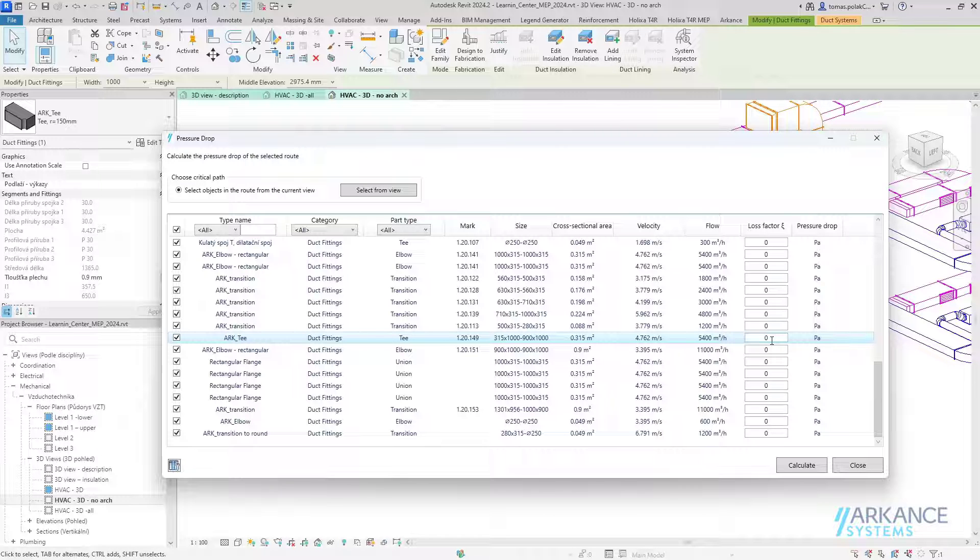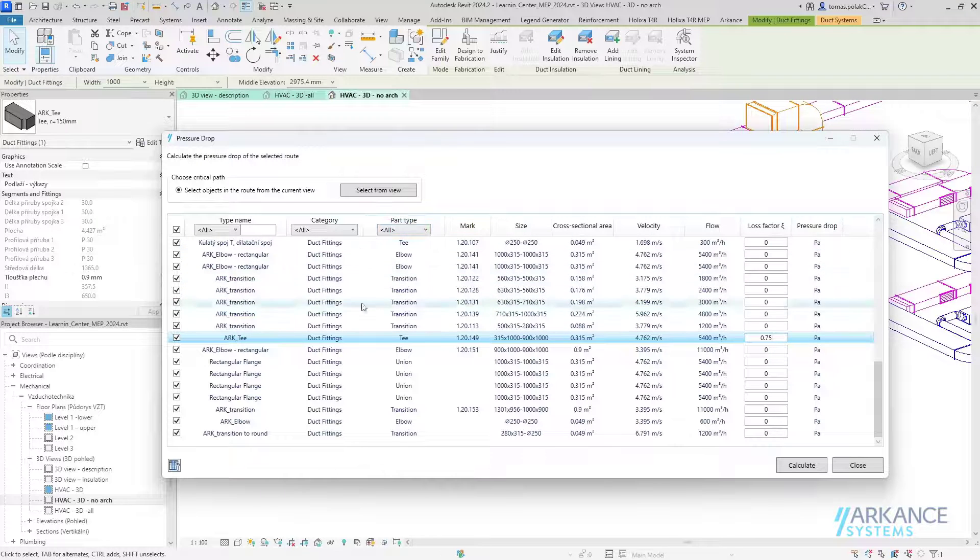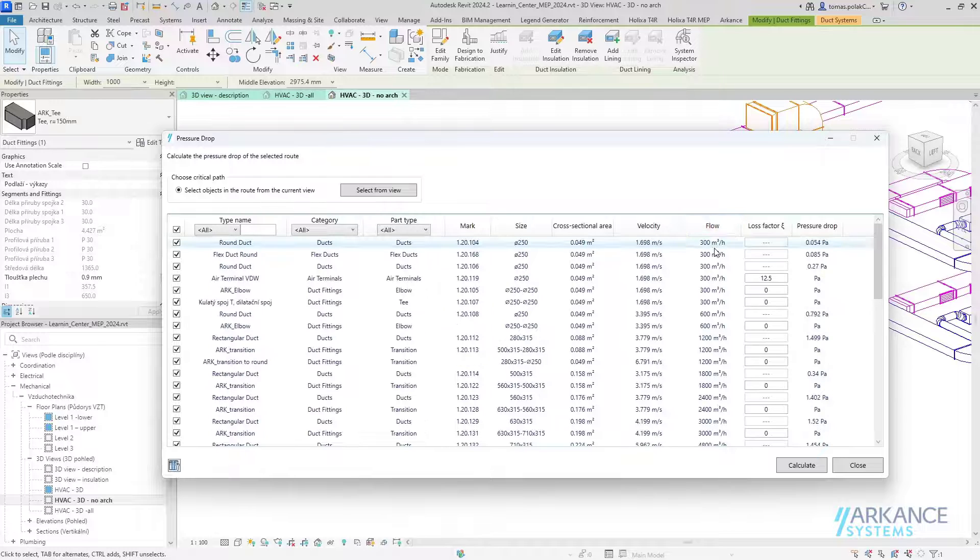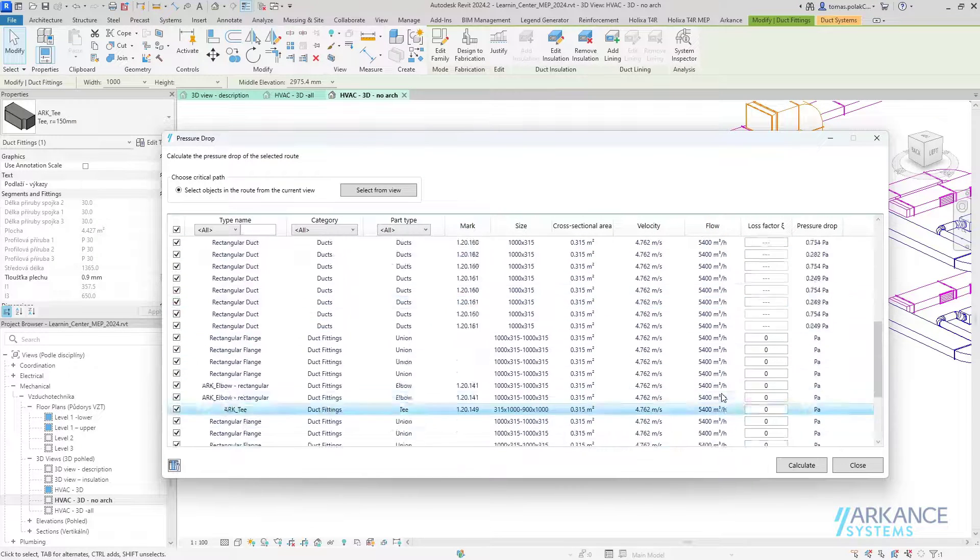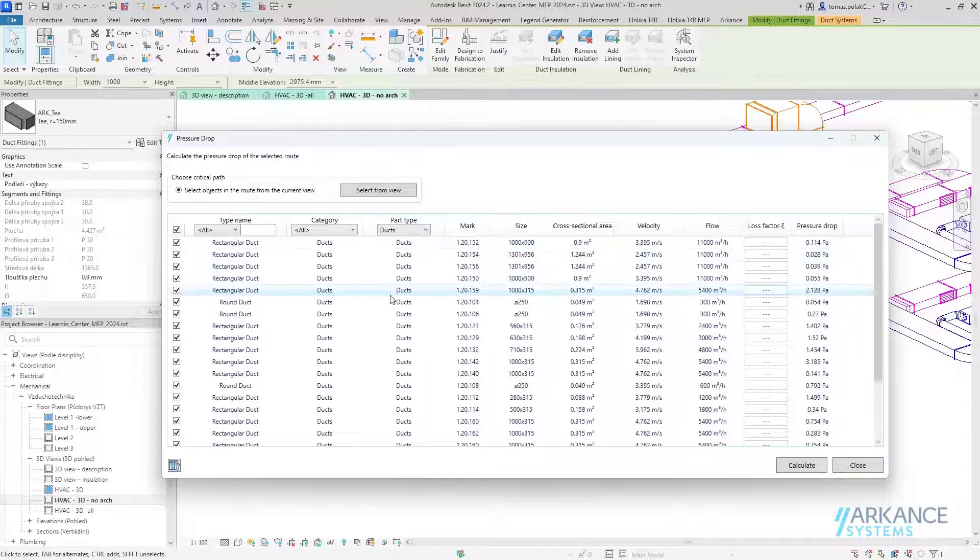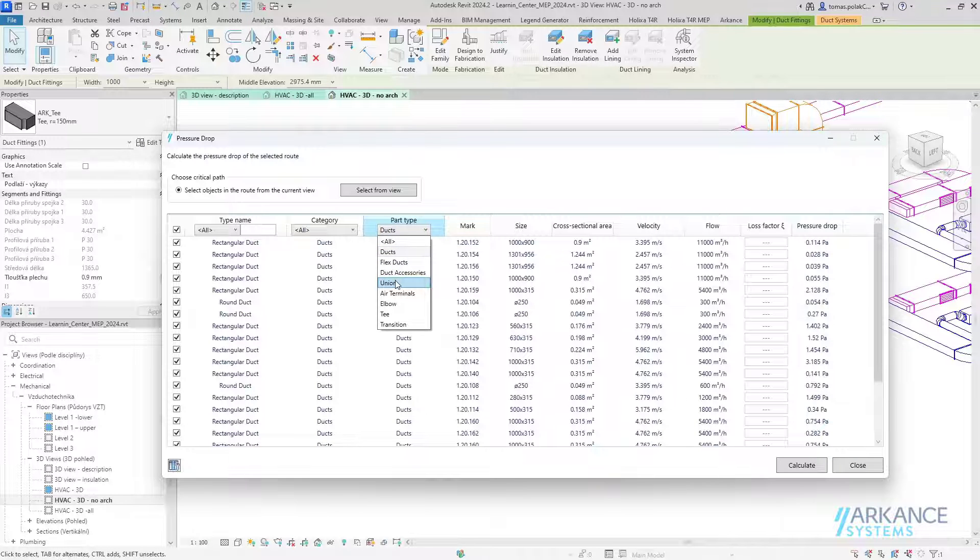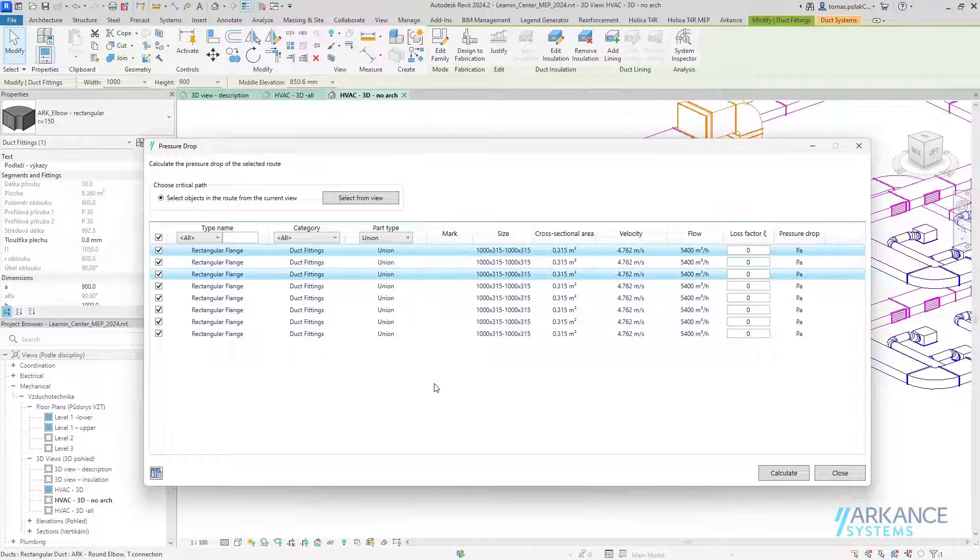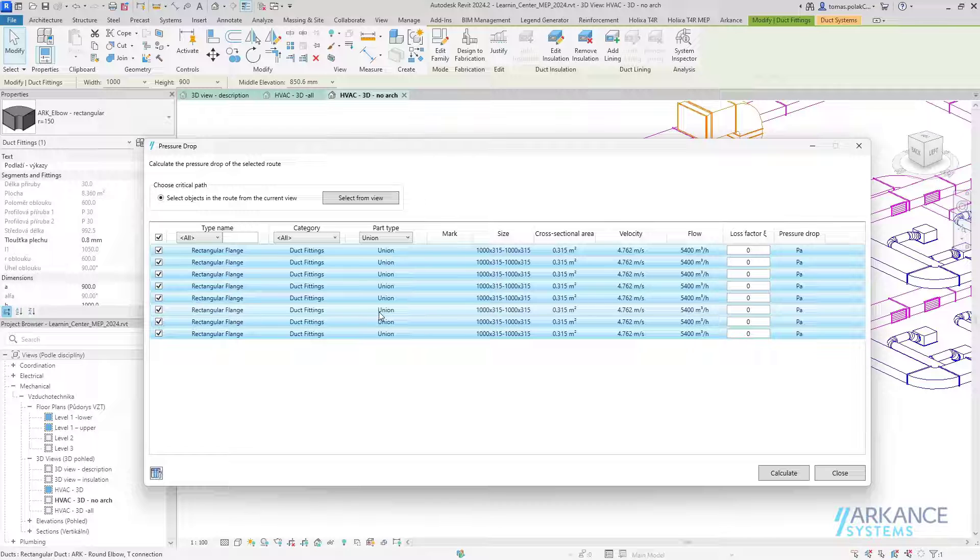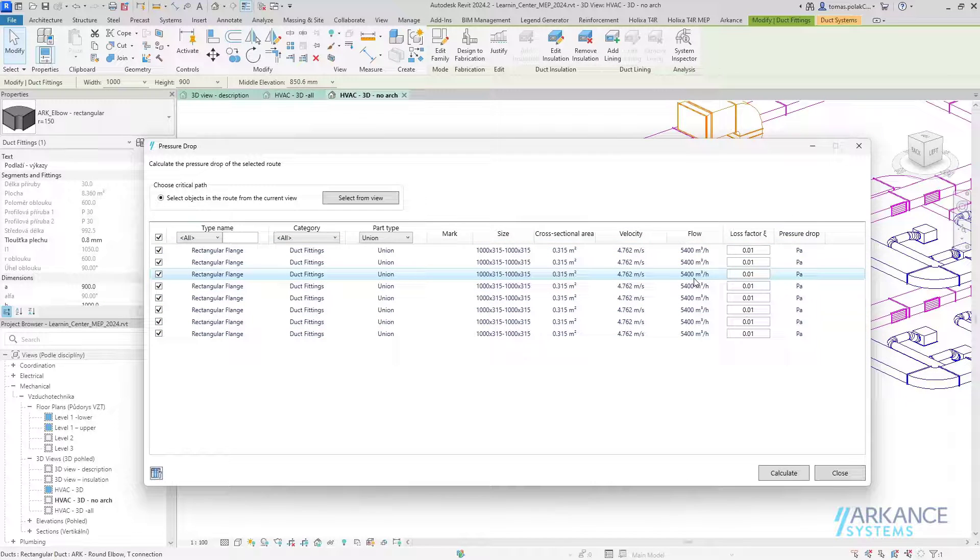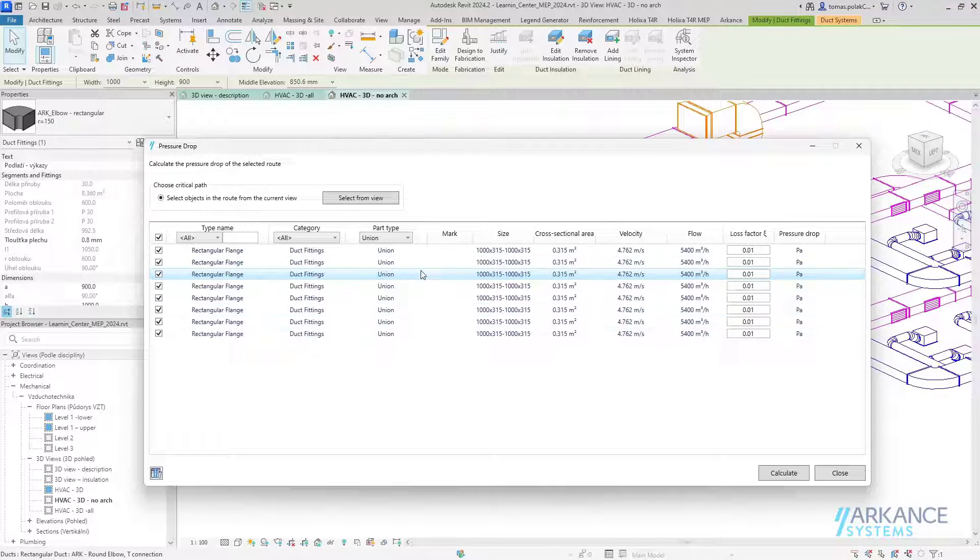I will add 0.75. Now you can sort or filter all of these elements. If I click on flow, I can sort them from lowest to highest. I can also filter by type. If I filter to unions, you can see all of the unions. I will shift-select to select all of the unions and add the coefficient of 0.01 to all of them.